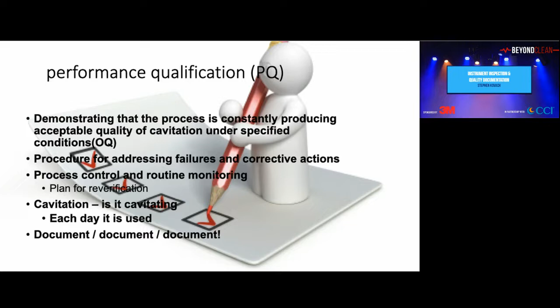There is peer-reviewed literature that shows many of the products that say they check for all forms and all the inputs of a sonic cleaner don't check for cavitation. They're really soil removal tests, and they're giving you a false sense. So how do you know your sonic's really working? So you put it in, you do your IQ, OQ, PQ, you test it every day with a proven test. If it doesn't pass, you then figure it out, you go and find out what's wrong with it. You should do this just like your sterilizer.